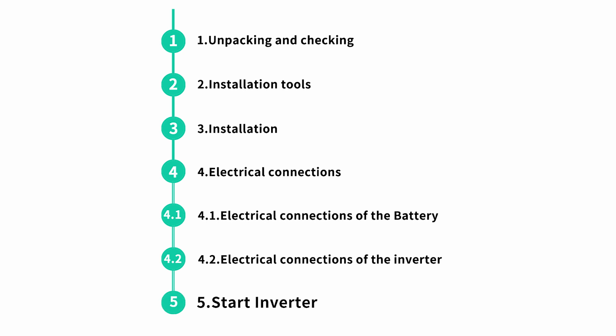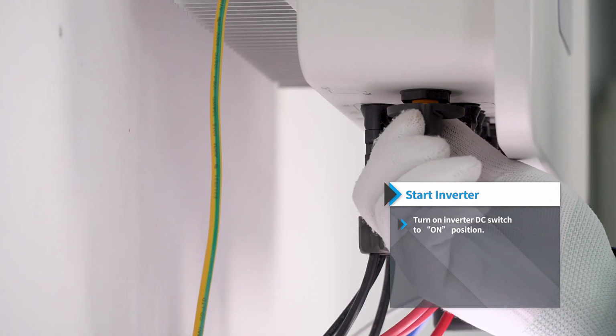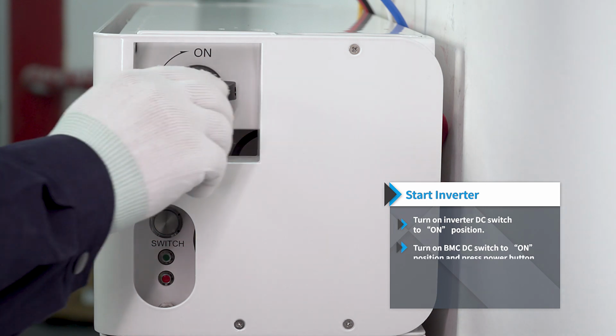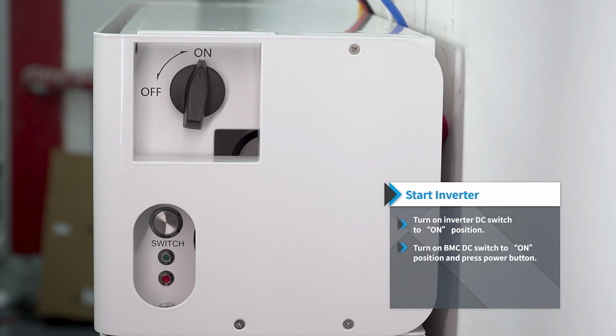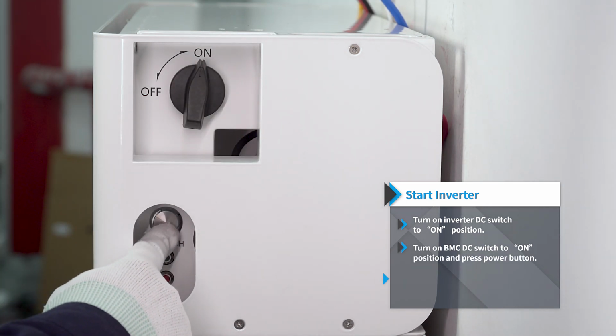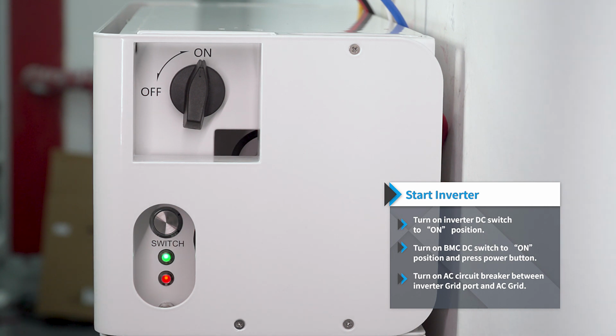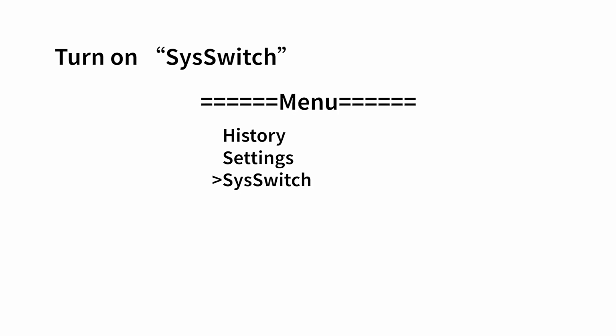Start inverter. Turn on inverter DC switch to on position. Turn on BMC DC switch to on position and press power button. Turn on AC circuit breaker between inverter grid port and AC grid. Turn on SysSwitch.